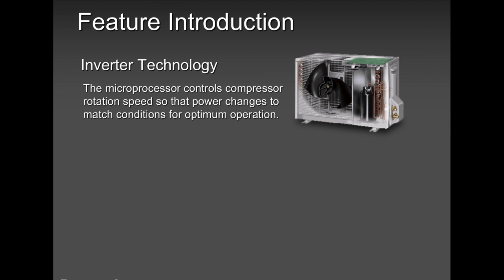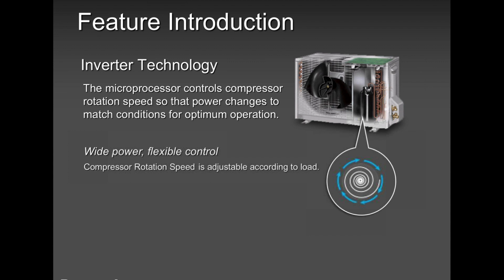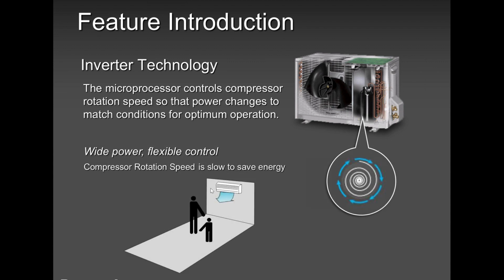And what tells the compressor, guys? What tells the compressor to run low and high? It's so simple. It's this load here. It's the load. Right now, the compressor, as you can see, it's running at a very low frequency. Why? Because the sensor has sensed the load, and the load is so little, only 2 guys, hardly generating any heat. Okay, so the compressor is going at a very slow speed.